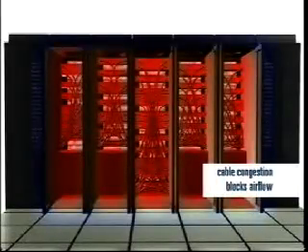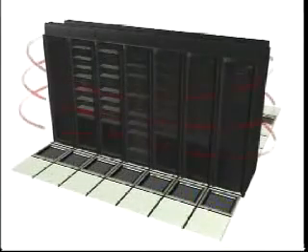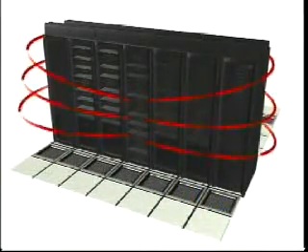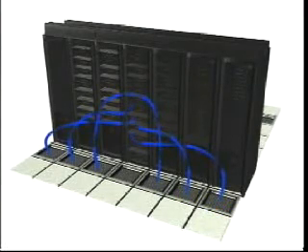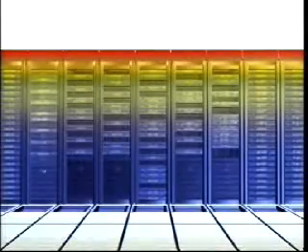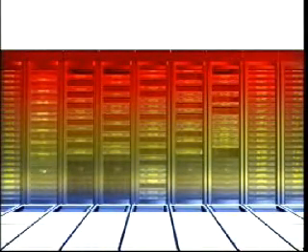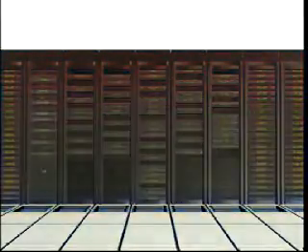Even more equipment is added, leading to higher power densities as well as cable congestion from additional network drops and power cords. Air recirculation increases. Because the new, denser servers cannot draw the necessary airflow from the raised flooring for proper cooling, they must pull the required air from another source. The air temperature across the entire room also begins to rise. As more heat is generated, the curtain of hot air at the top of the room is lowered closer to the rack inlet. The cooling situation in the data center becomes critical.